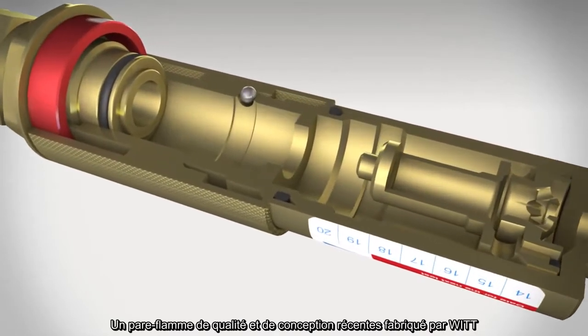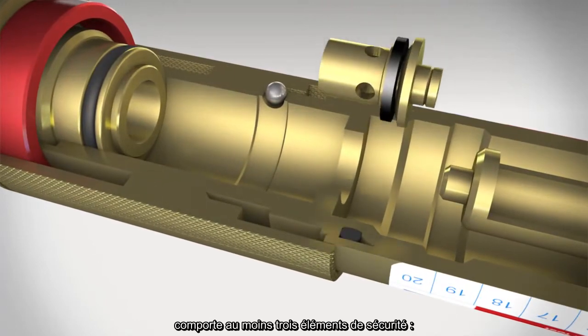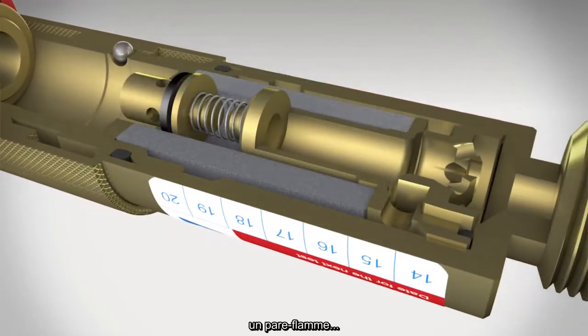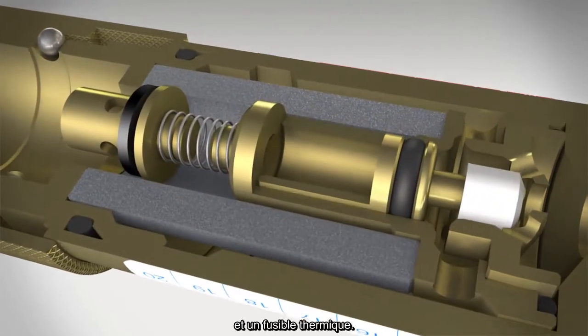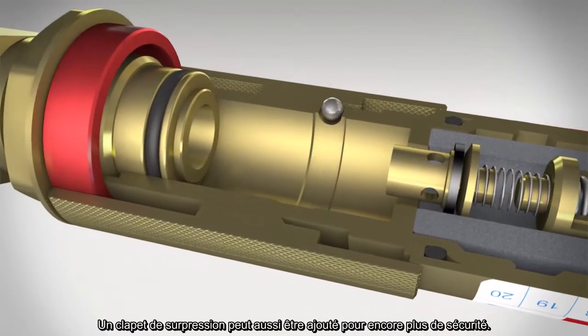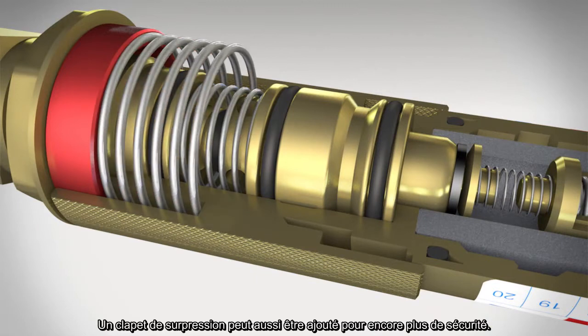A modern quality flashback arrestor made by WITT has at least three protection elements: a gas non-return valve, a flame arrestor, and a temperature-sensitive cutoff valve. A pressure-sensitive cutoff valve can also be added, ensuring maximum safety.